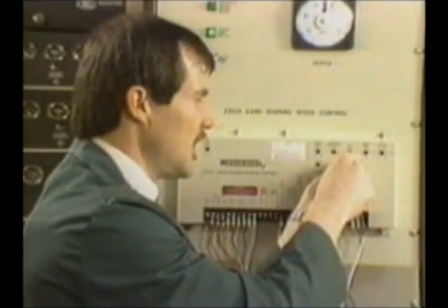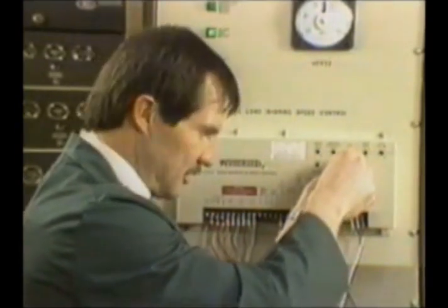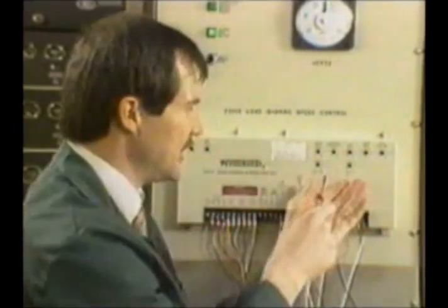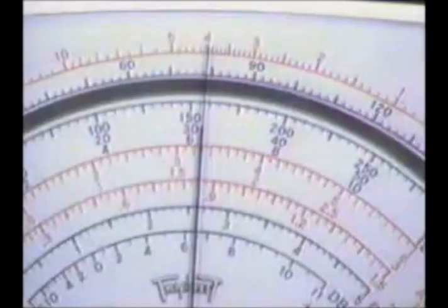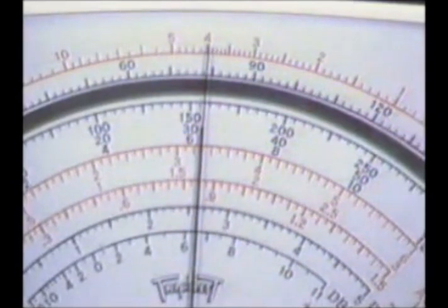The reset potentiometer will not always make you go unstable fully clockwise. As right there, I'm fully clockwise, but I'm not unstable. Well, now, what the reset will do for your response time of the prime mover is when you go off a speed, it's going to keep you from coming back and overshooting that speed. It's going to pull you back into speed smoothly.